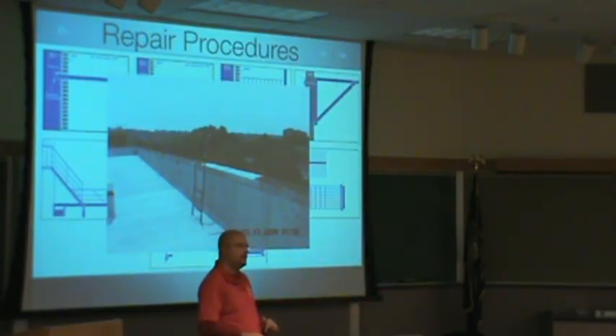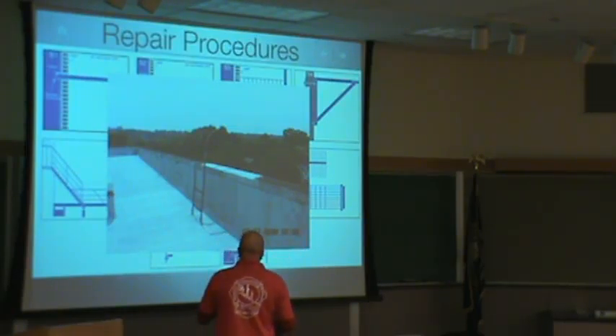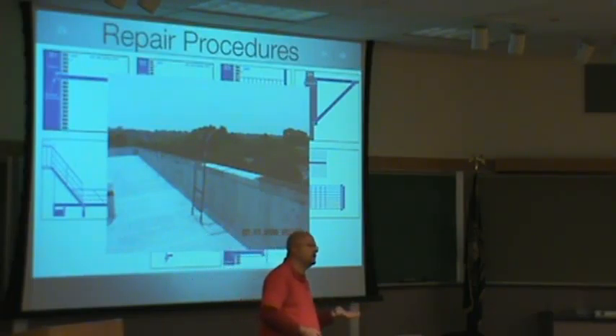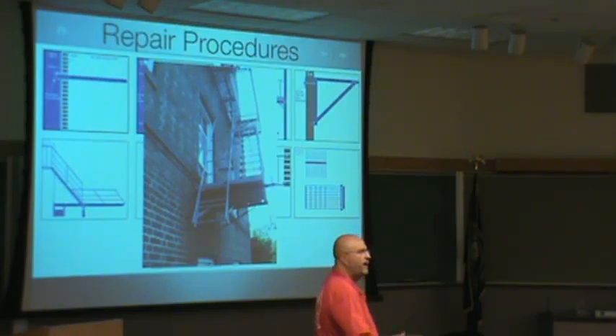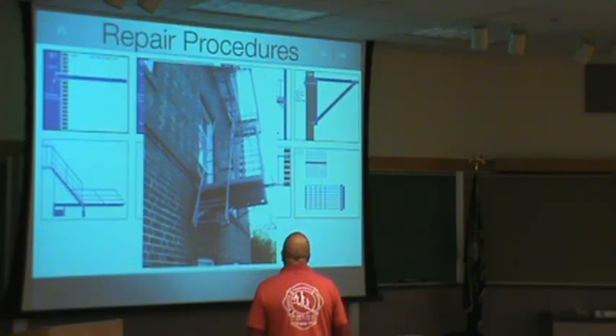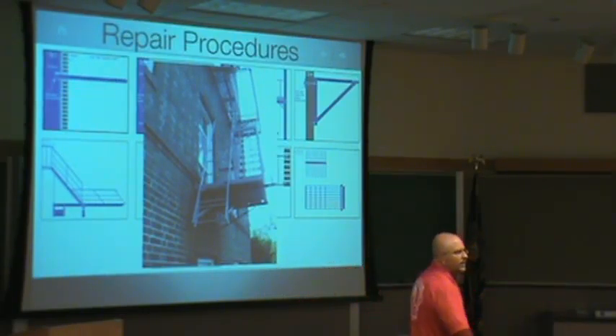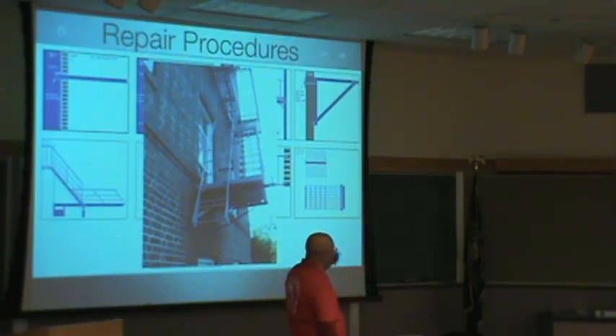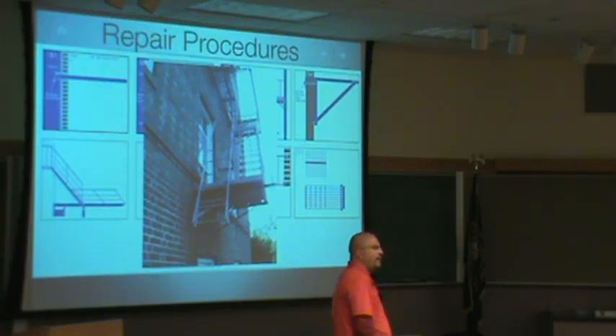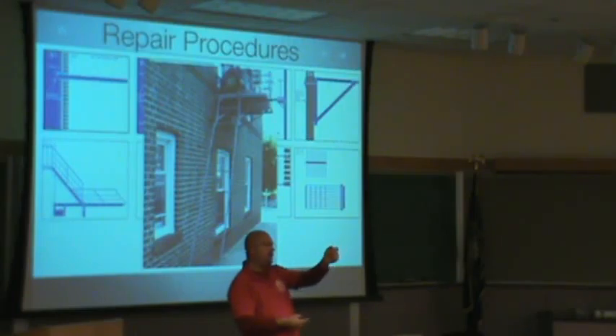Ladders over the roof — these must be secured for you firefighters. Nobody's climbing up fire escapes but you guys. These ladders must be confirmed in good condition for your firefighters to get up and blow a hole in the roof to start the ventilation process. These are also illegal — people have modified their ladders. Instead of putting weights on them, they basically cut them in half so it flops out. We call this Thor's Hammer. When you push this out — whether a little kid's playing up there or the wind blows — that ladder comes out like Thor's Hammer in a nice arching swing. When the tip of that ladder gets you on the head, it drives you like a nail into the ground. These are illegal.